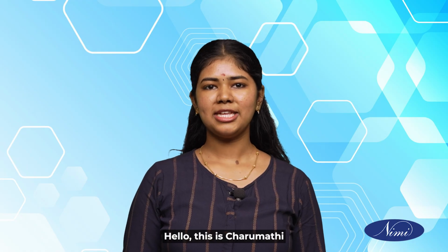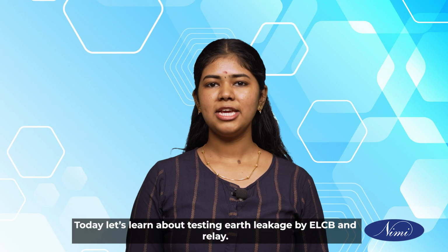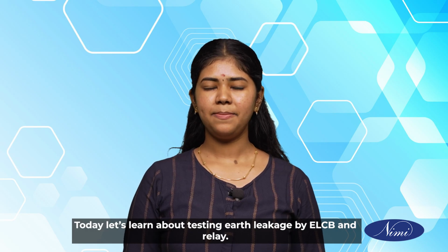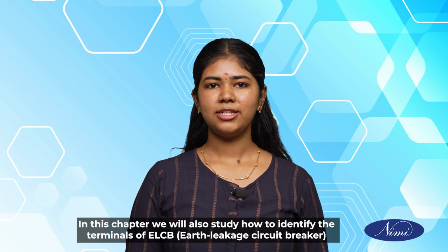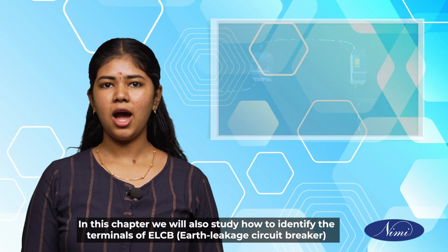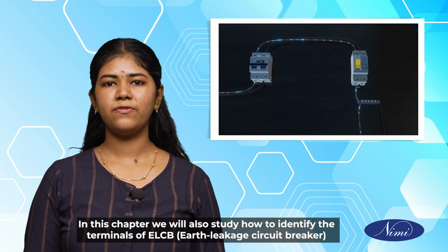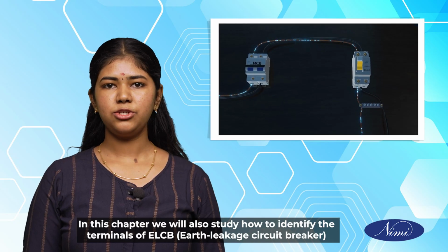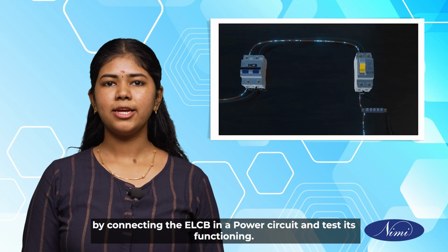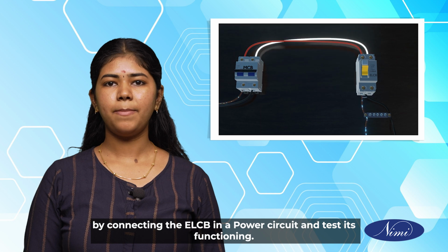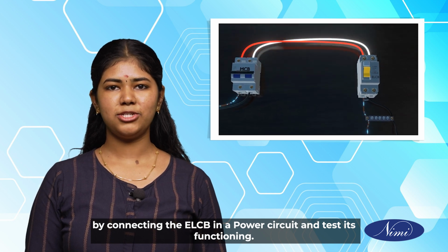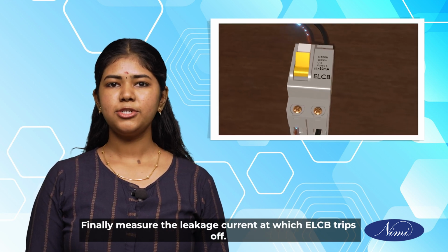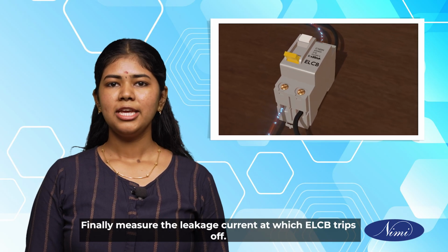Hello, this is Charumati. Today, let's learn about testing earth leakage by ELCB and relay. In this chapter, we will also study how to identify the terminals of ELCB, earth leakage circuit breaker, by connecting the ELCB in a power circuit and test its functioning. Finally, measure the leakage current at which ELCB trips off.